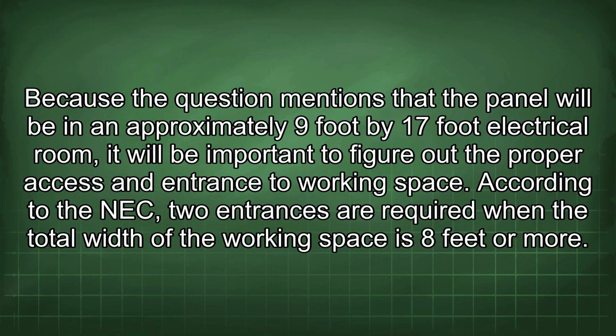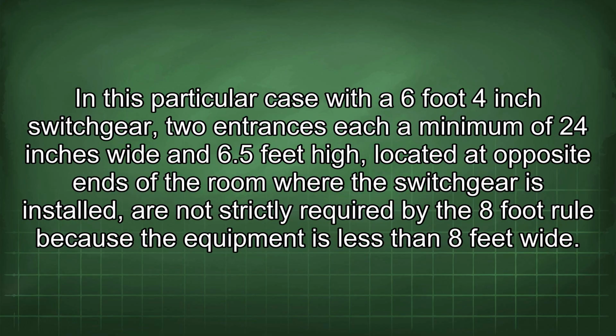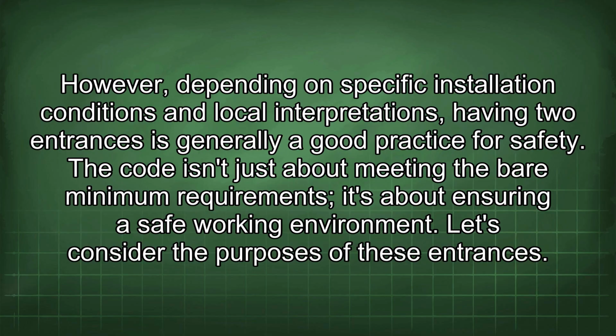According to the NEC, two entrances are required when the total width of the working space is 8 feet or more. In this particular case, with a 6 foot 4 inch switchgear, two entrances each a minimum of 24 inches wide and 6.5 feet high, located at opposite ends of the room where the switchgear is installed, are not strictly required by the 8-foot rule because the equipment is less than 8 feet wide. However, depending on specific installation conditions and local interpretations, having two entrances is generally a good practice for safety. The code isn't just about meeting the bare minimum requirements, it's about ensuring a safe working environment.